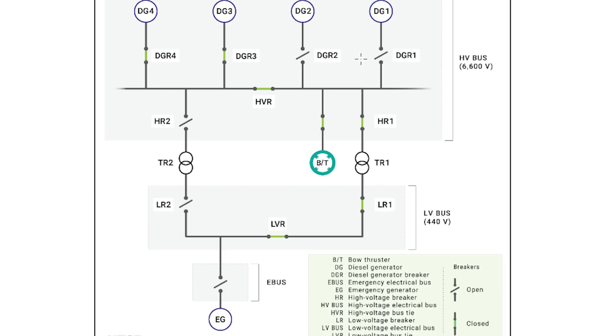There are two power buses on this ship: the high voltage one at 6,600 volts, and a lower powered bus at 440 volts. This lower bus powers other equipment like the emergency generator, most pumps, lighting, emergency lighting, and other systems that don't need 6,600 volts. The voltage from the 6,600 volt bus passes through a transformer with enough windings to convert it down to 440 volts.